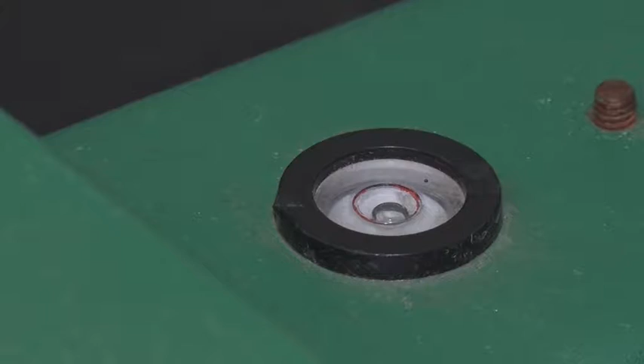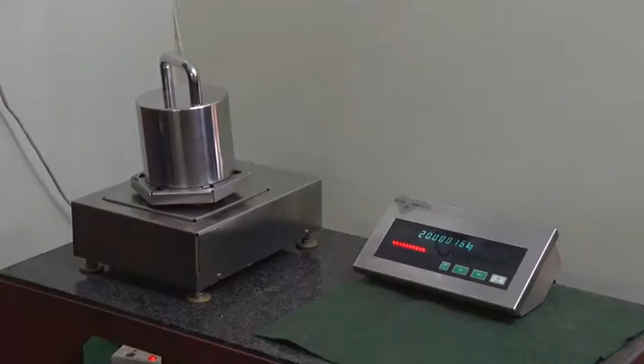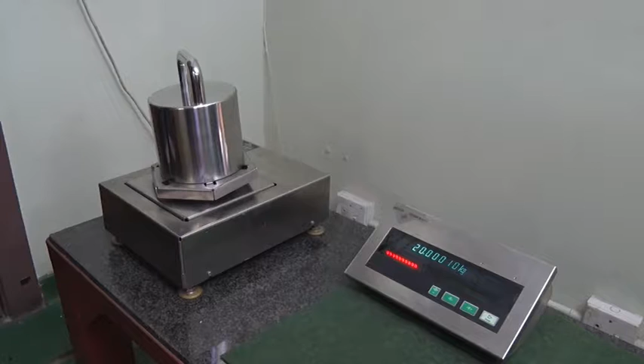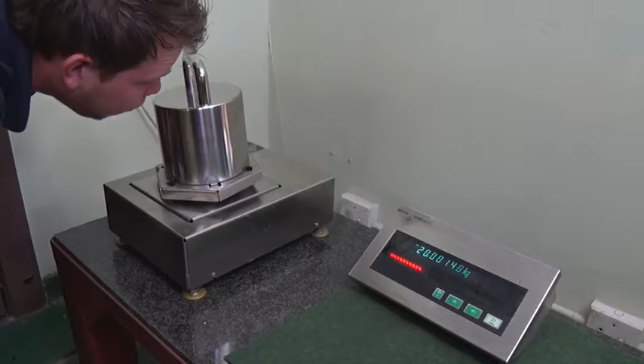You will need to check the leveling, which is done visually with the spirit level. When calibrating the scale, you will need to wear gloves when handling the test weights. If test weights are magnetized, touched, or dirty in any way, this will affect the weight itself and therefore the accuracy of the reading. Rooms are temperature controlled to ensure the accuracy of the balance, and the lab is kept at an average of 23 degrees for this reason.